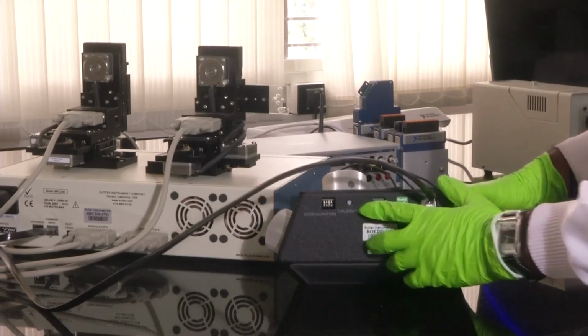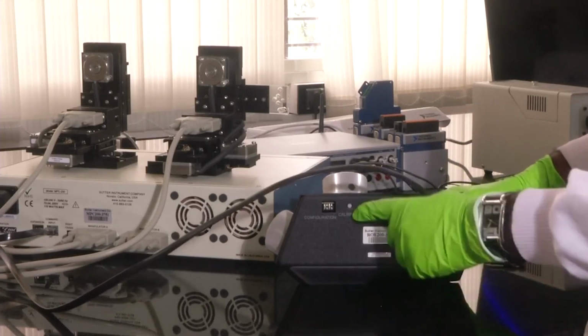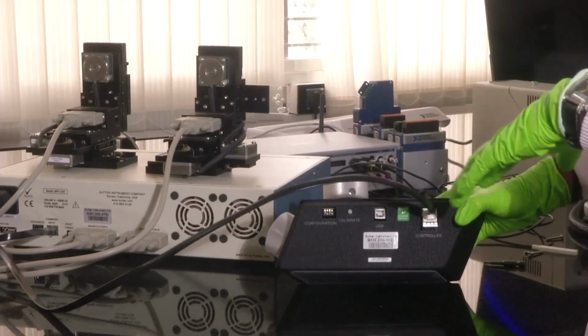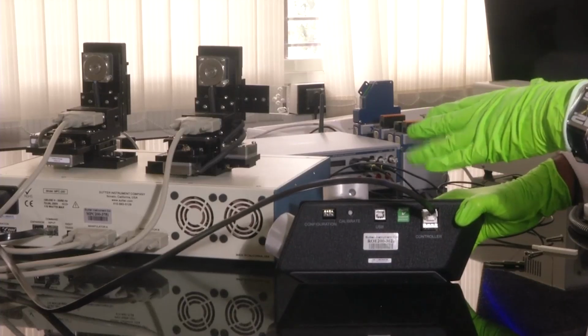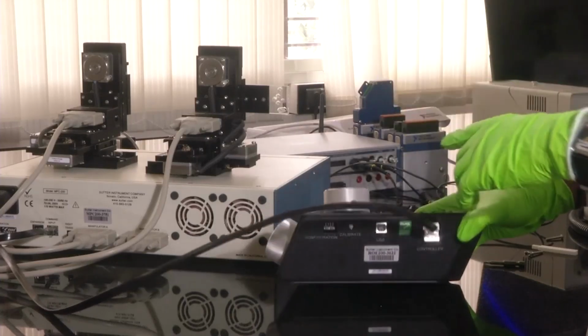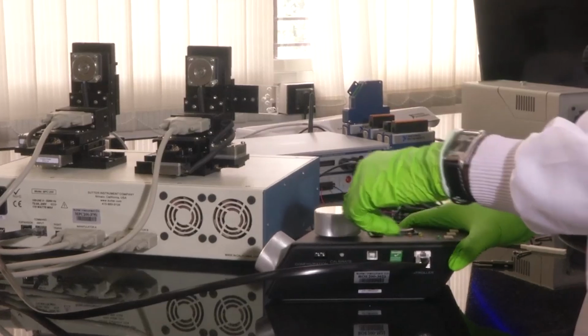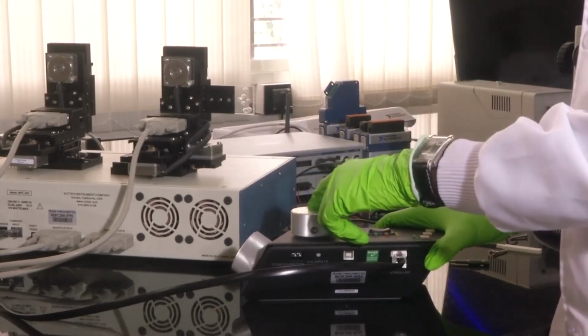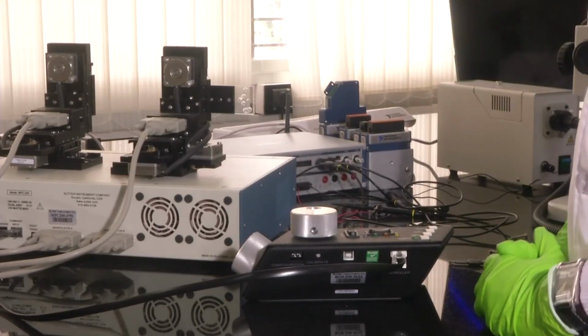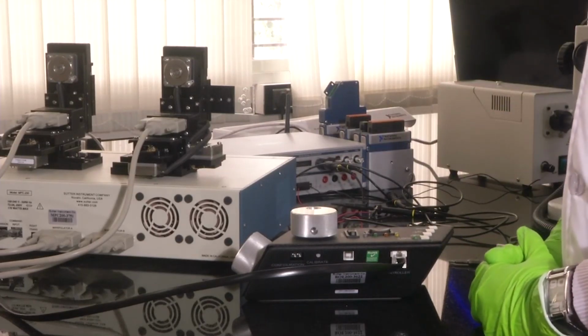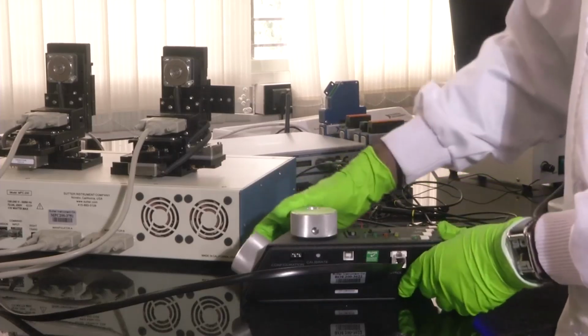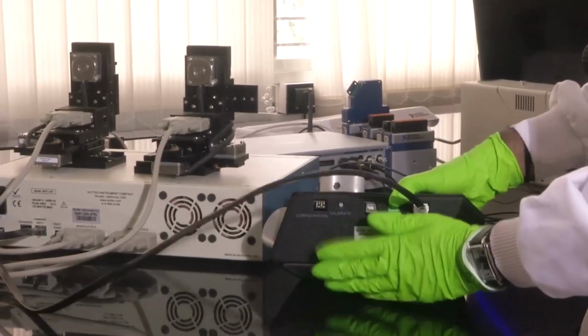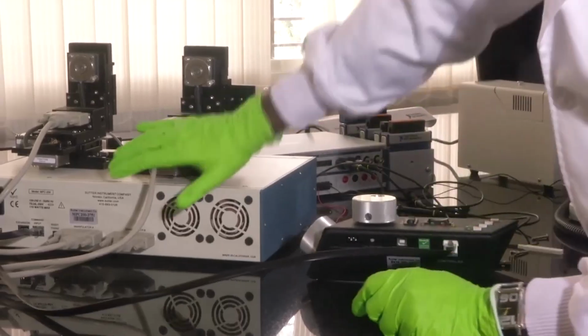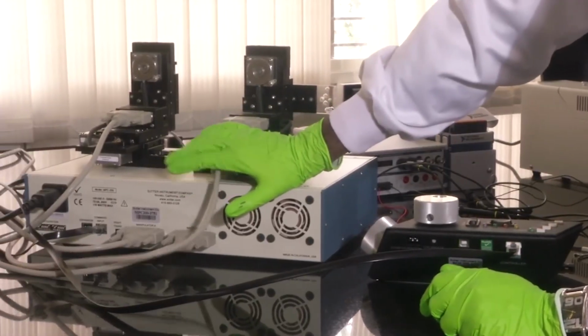So, these are the only ports that are there in the manipulator, and there is a calibrate button here. Once power is turned on, if you press calibrate, the manipulator will calibrate its movements and make sure that when we make a movement of 1 micron in the control unit, there is actually a movement of 1 micron on the manipulator. So, that is what you call calibration. That is how you do the calibration. These are the main ports available on the back side of the control unit, and those are the ports available in the main unit.